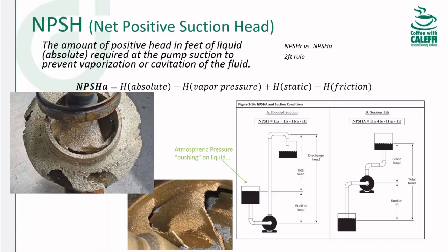And for even more layman's terms, and trust me, I was there. I deal with electrons, not really water molecules. But for me, the way it finally snapped was, think of a piece of string, and let's say you need to pull a weight across your desk. If you just yank it as fast as you can, you're going to snap the string. But if you pull slowly, everything will be fine. So kind of like that, that's why 3600 RPM pumps have a higher NPSH requirement than 1800 RPMs and slower spinning impellers.